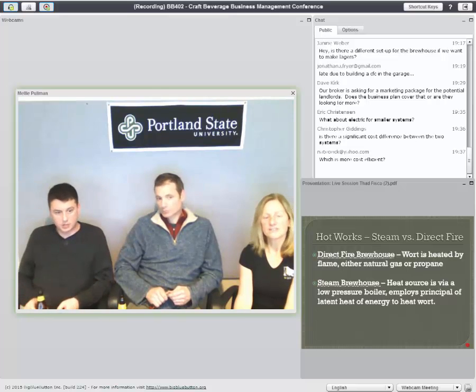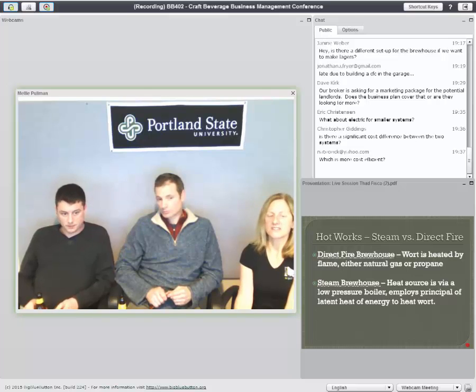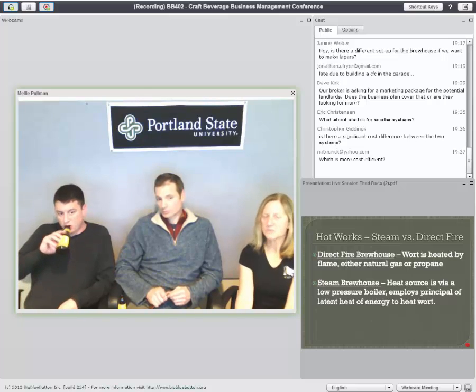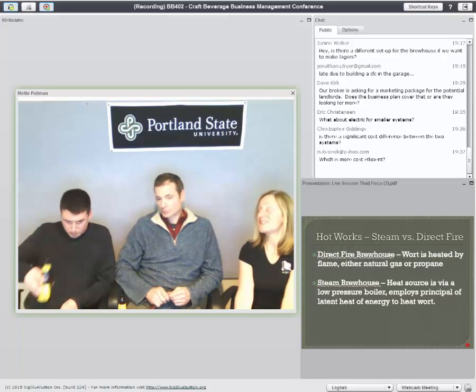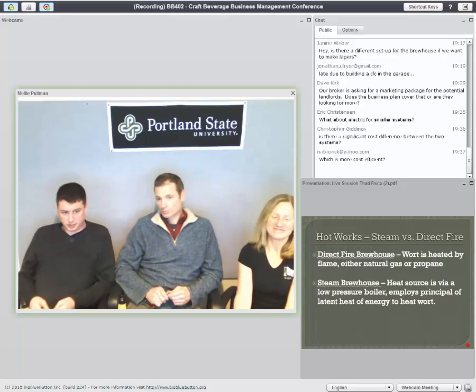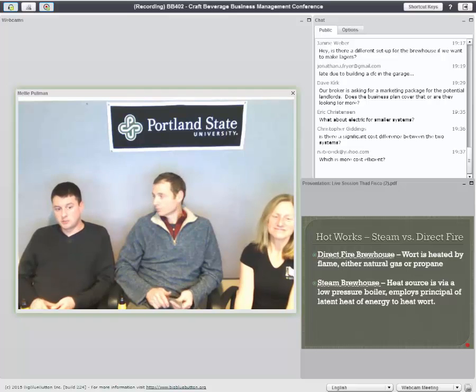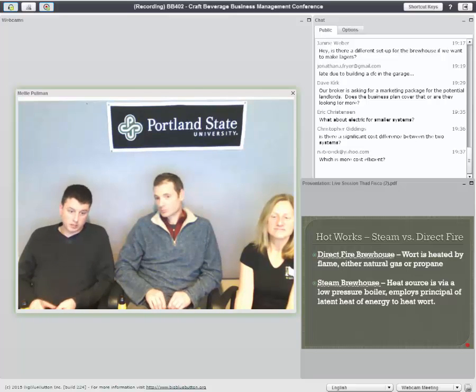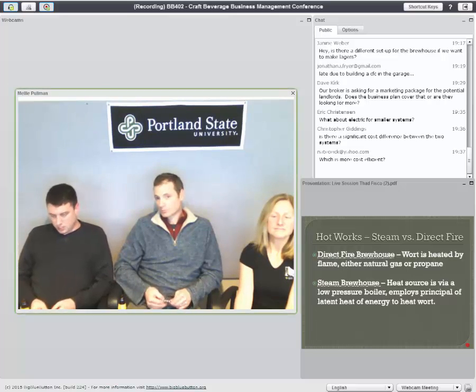Chris and Nate are getting at two different things: is there a significant cost difference between the two systems, and which is more cost effective? We've built it so that between the direct fired and steam system, steam is exactly 7% more expensive. But then you have to add the cost of the boiler in - for a 7-barrel system, that can end up being another $16,000 to $18,000 to go steam.